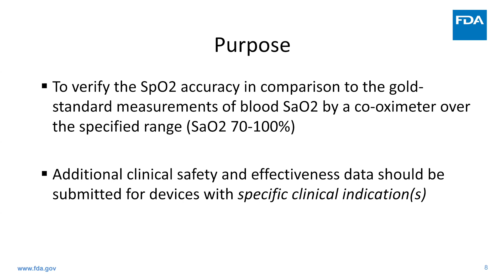Regarding the subjects, as you know, per Annex EE of ISO 80601-2-61, the pre-market desaturation study should include a sufficient number of patients or subjects to attain statistically significant information to demonstrate a specific SpO2 accuracy. Furthermore, a minimum of 200 pooled data pairs, SpO2 and SaO2, distributed evenly over the testing range, the aforementioned 70 to 100%, with a minimum of at least 10 healthy volunteers, is recommended.